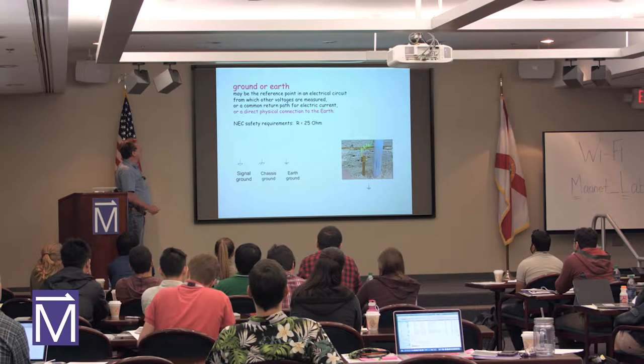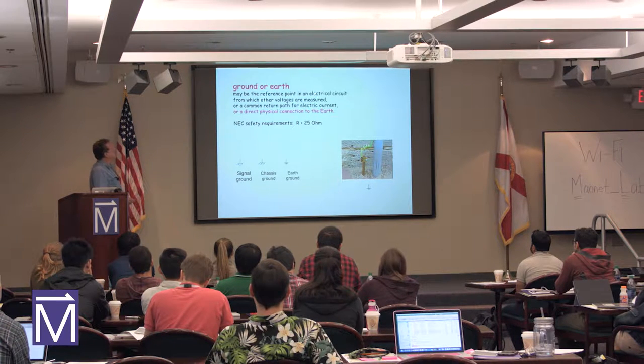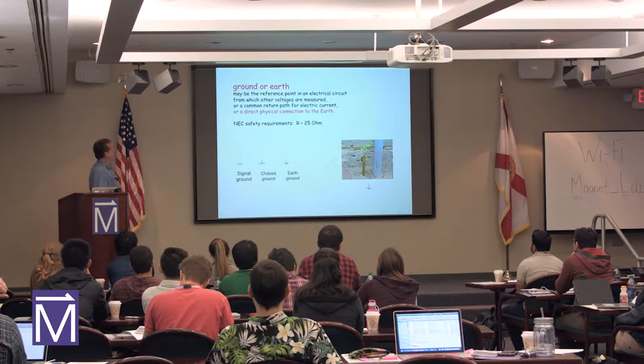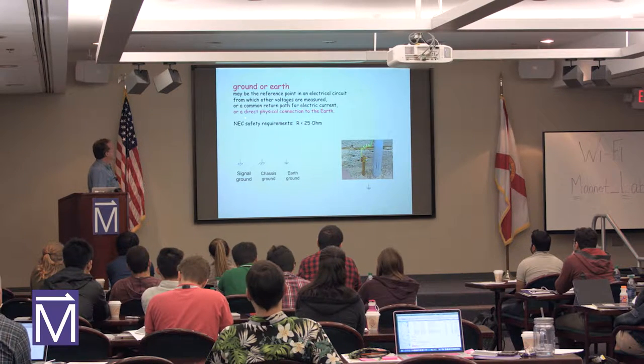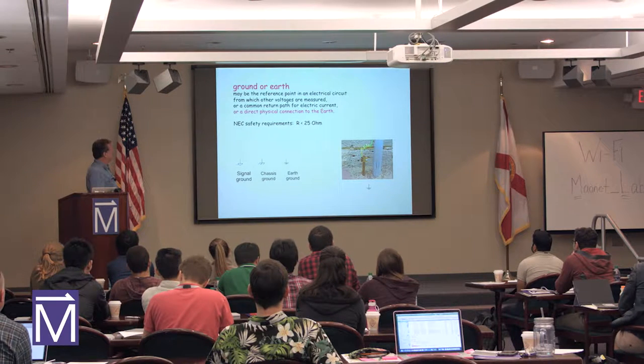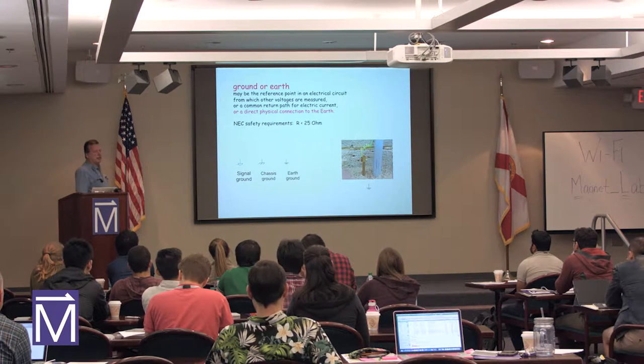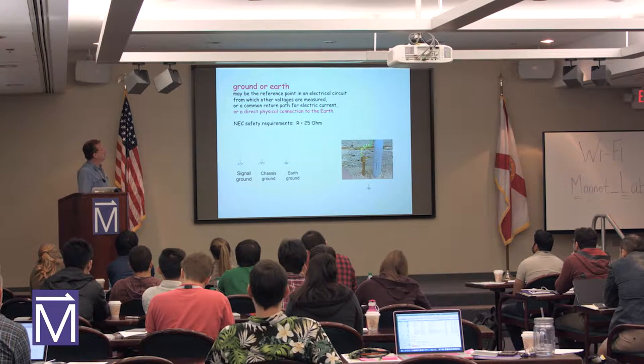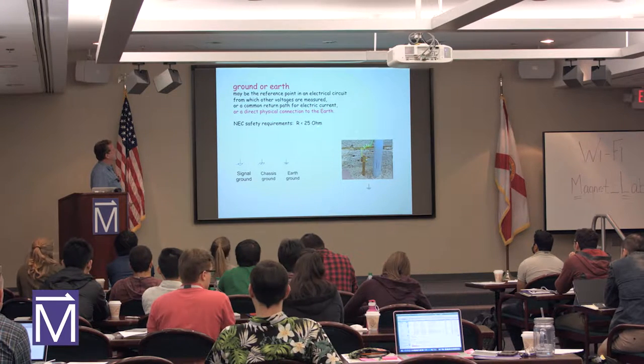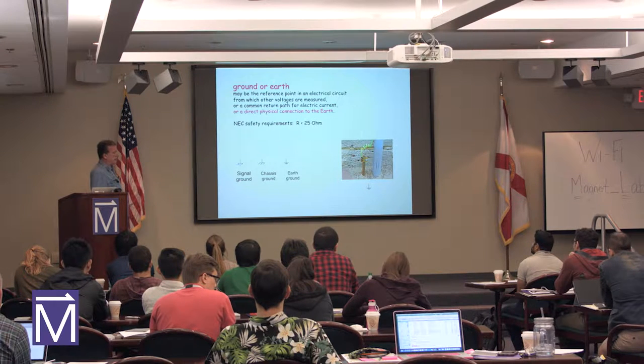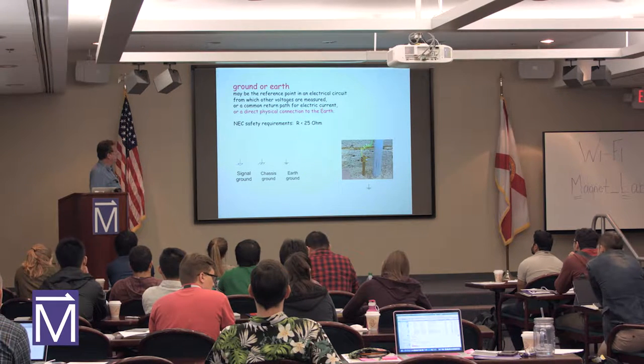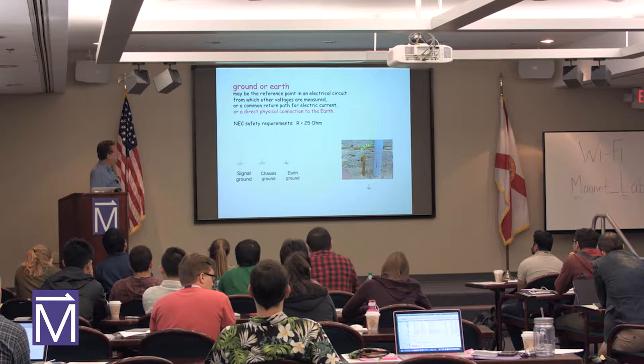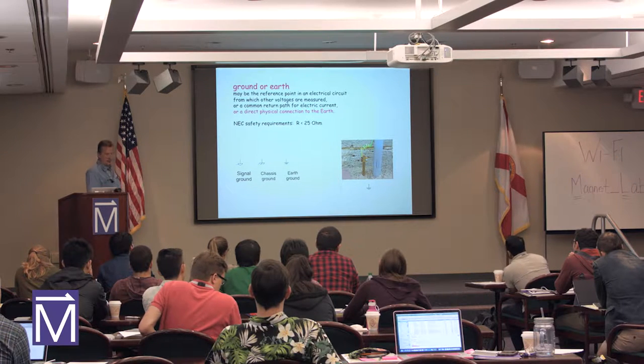What is ground or earth? Maybe the reference point in an electrical circuit from which other voltages are measured, or a common return path for electric current, or most commonly a direct physical connection to the earth. Safety requirements in the US are that grounding should be no more than 25 ohms to the earth. This is the typical designation of real earth, and this is how it looks. It goes really to the earth.